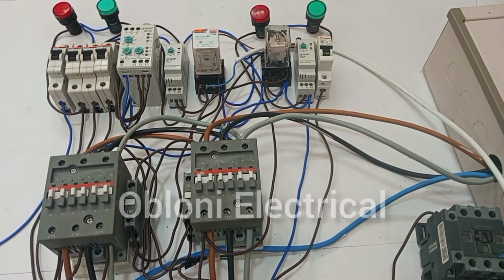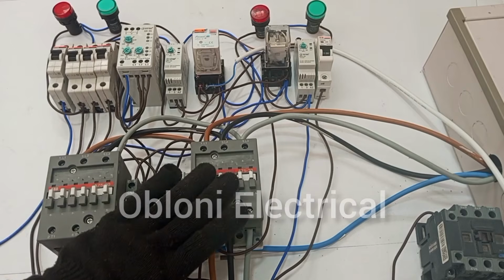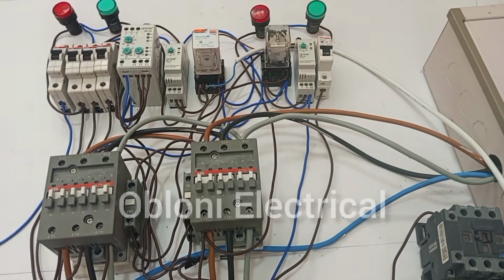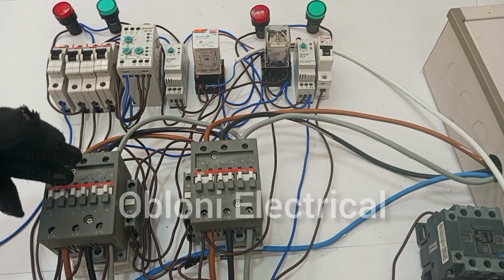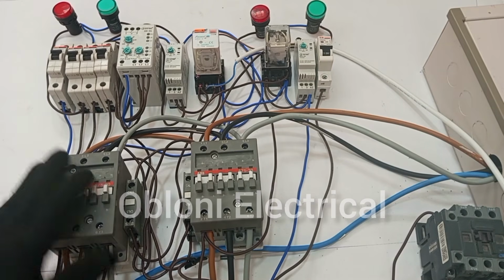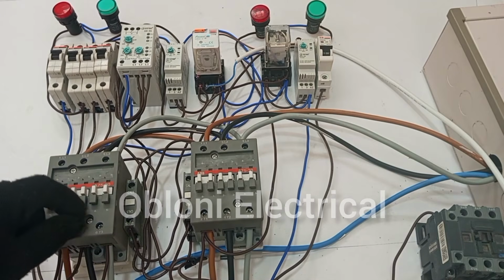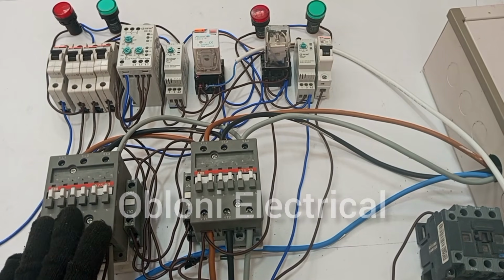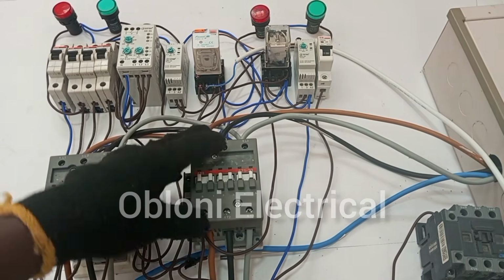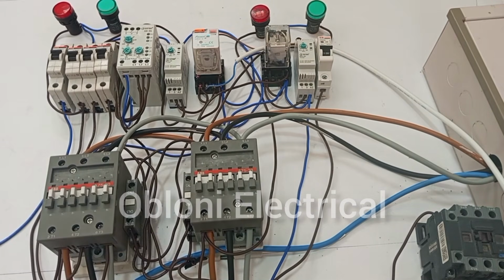So at this point, we have this system in a way that anytime the main supply is available, it signals the generator to turn off. And then the contactor for the main supply closes to supply power to the load. Good. And then as soon as the main supply goes off, the same connection we have done sends signal to the generator controller to start and then supply power to the load. All right, so briefly, let's look at how it works.